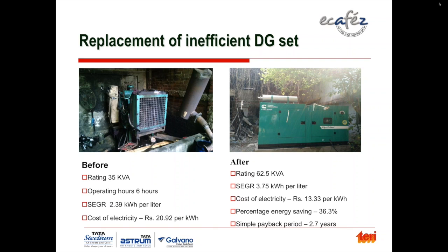Whereas the new SEGR, the one after replacement, this is with a higher sized DG set because they required it for other loads also, was 3.75 units per liter, compared to 2.4 units per liter earlier.